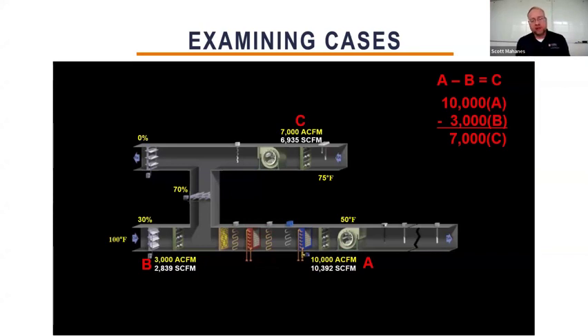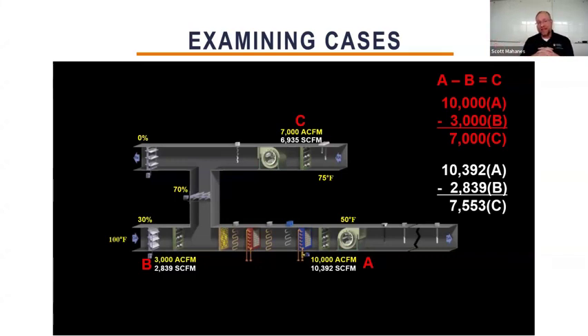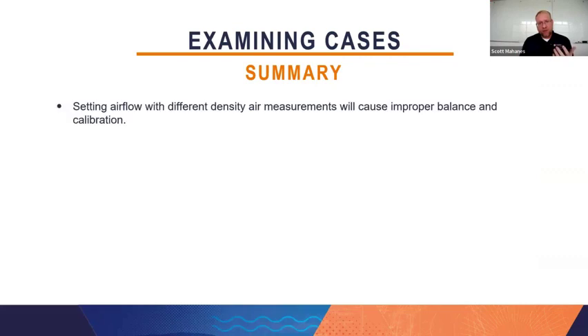And if you convert these into what they really are in mass, the ABC comparison is very different. A minus B equals 7,553 at C, and C is not at 7,553, it's at 6,935. And so you have an 8% error. Okay. In summary, when setting airflow, different density air measurements are going to cause an improper balance and/or calibration. And we've seen this with the VAV example, with our comparative airflow station example, and with constant volume fan setup.